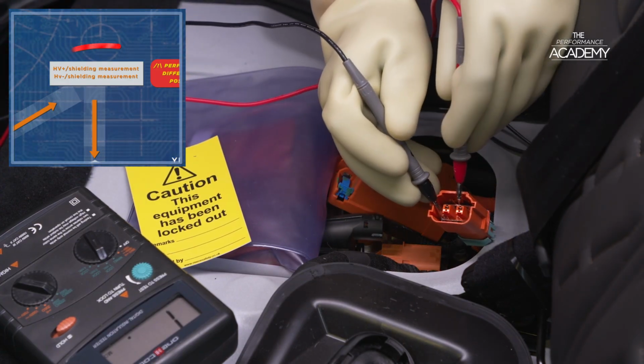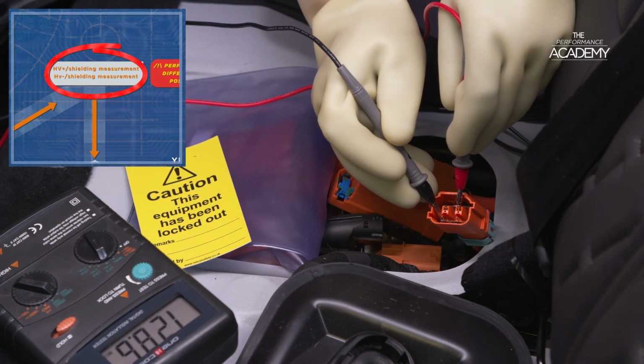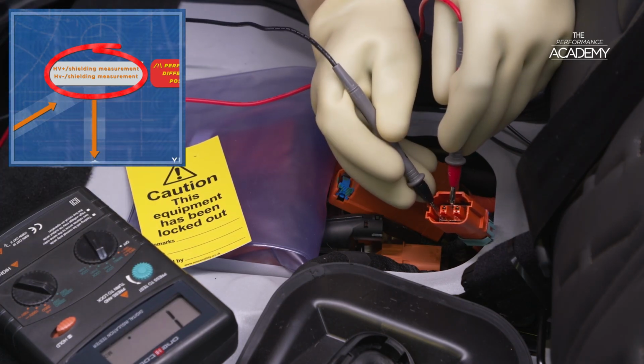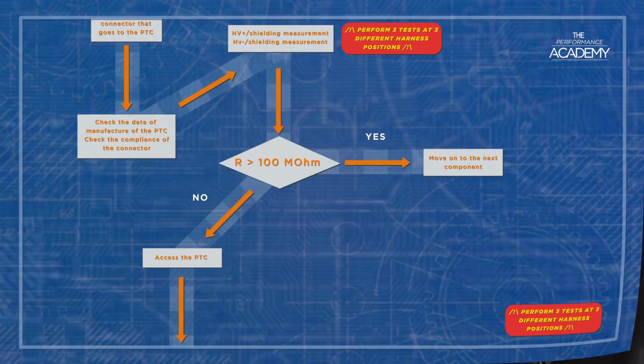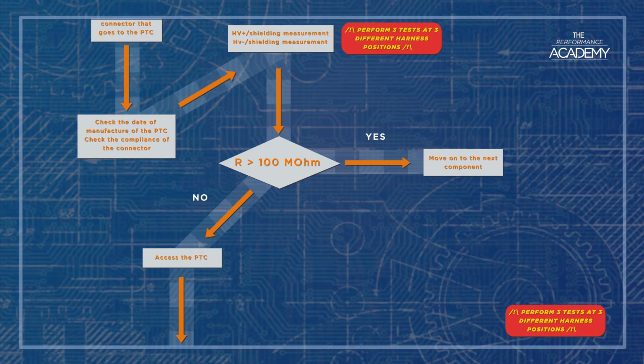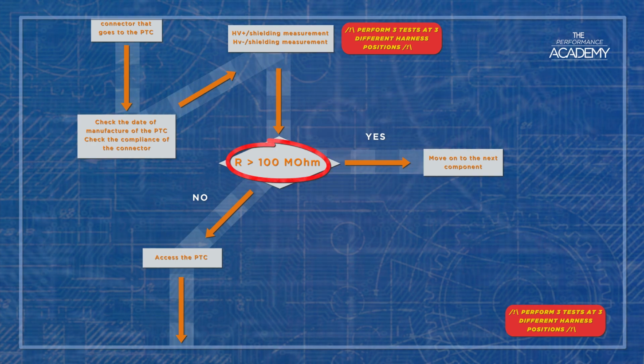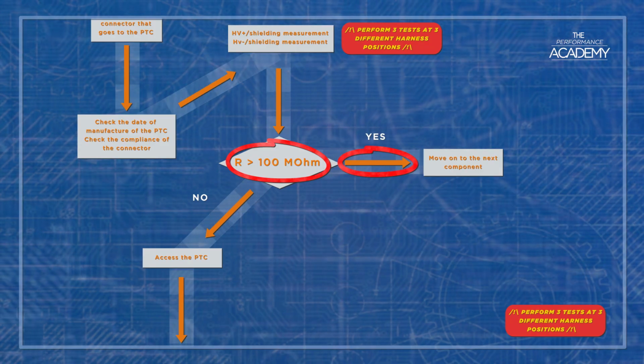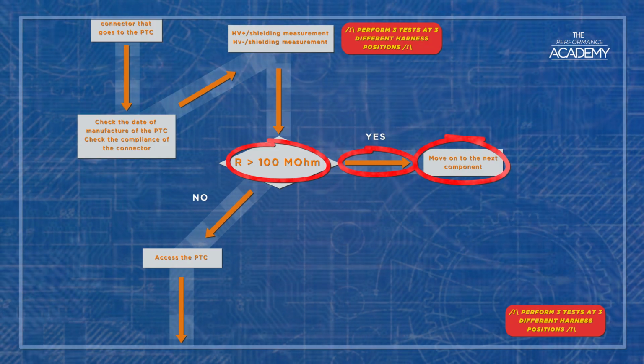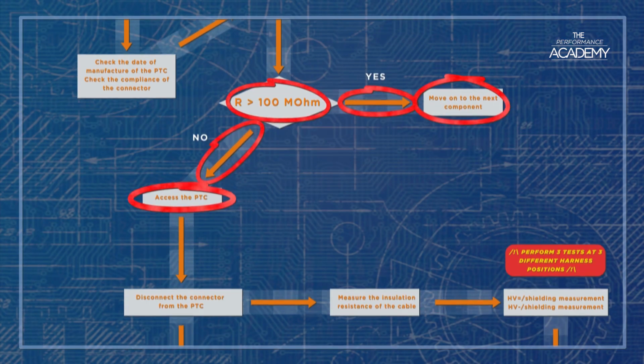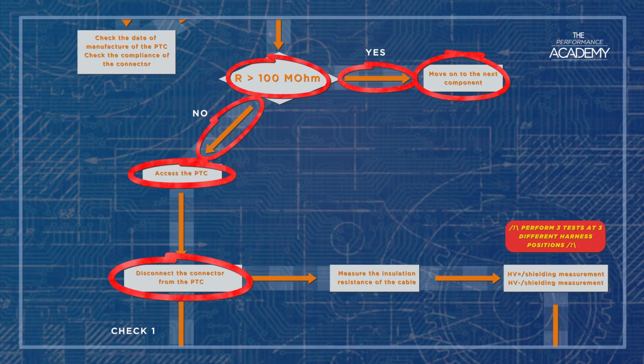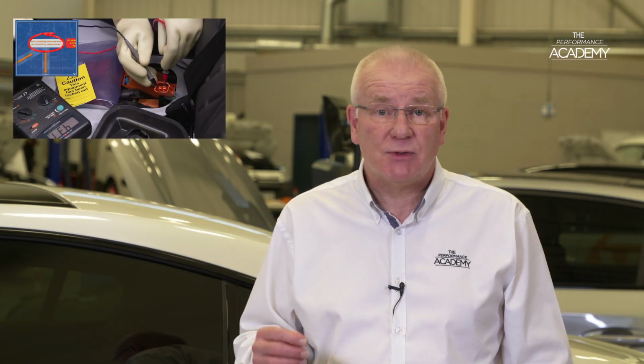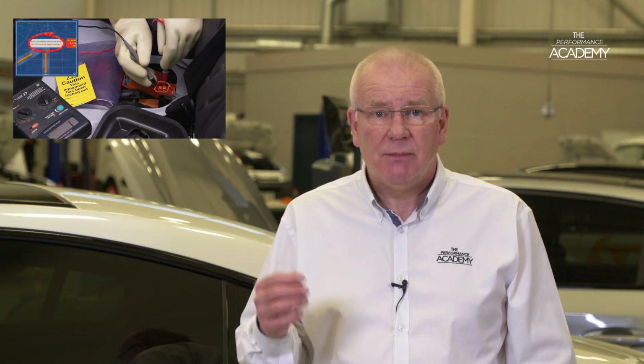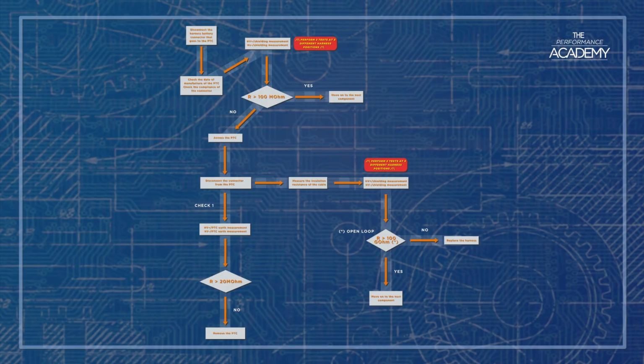High voltage plus to shielding measurement, followed by high voltage minus to shielding measurement. After recording the results, following the flowchart down to the either or results box, which states if R is greater than 100 megaohms, result yes. Move on to check the next component. Result no. Disconnect the high voltage cable connection at the PTC heater itself. However, this was a good result with a reading which scrolled up to infinity or 1. But let's assume we had a reading of less than 100 megaohms.